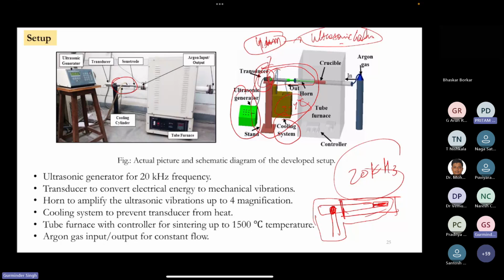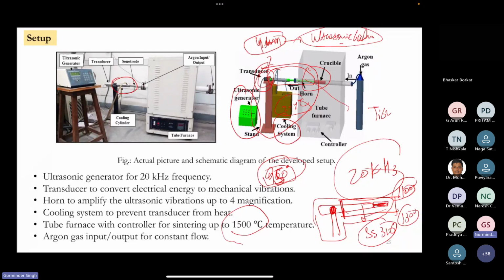But there is a limitation. This horn is of stainless steel SS 316, which you can't use above 1300 degrees Celsius, because it has vibration lag starting from 1100 degrees Celsius. We have done it at only 900 degrees Celsius. The furnace can work up to 1500 degrees Celsius, but we have only worked at 950 degrees Celsius maximum, because otherwise you need a titanium Ti64 horn, which can go up to higher temperatures.